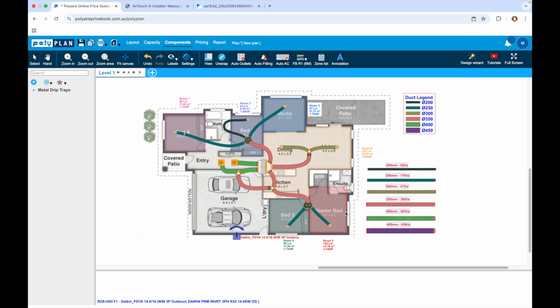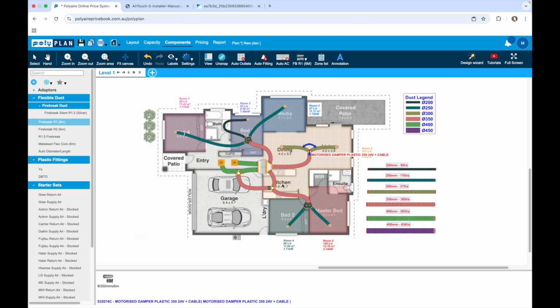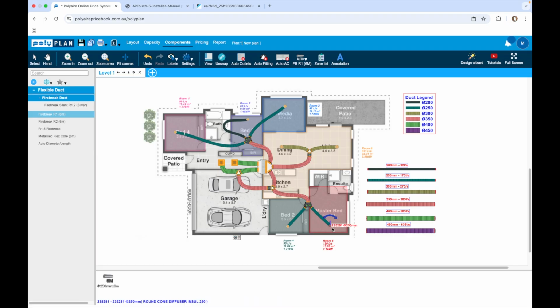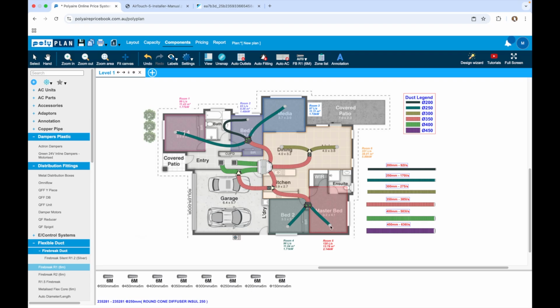So to get past that, I think they just decide that this spill area here gets cooled to the coldest set point. As this heats up 1 degree, this opens again because the unit's already running and dumping cold air in here. It can dump some more cold air in here and it maintains that temperature perfectly. So most of the time with a spill, if you're sleeping in all these other rooms at night and doing things, these temperatures will stay perfect all day, all night. But this area here is going to end up getting too cold, colder than you want, and you're paying to cool all of this down. It's typically why you don't want to be using these.